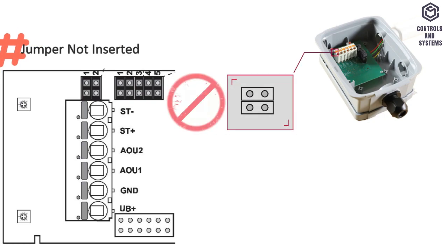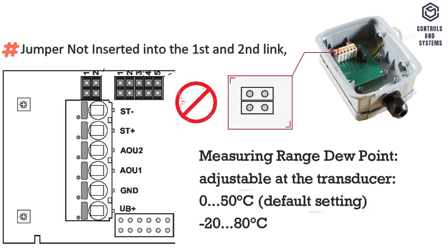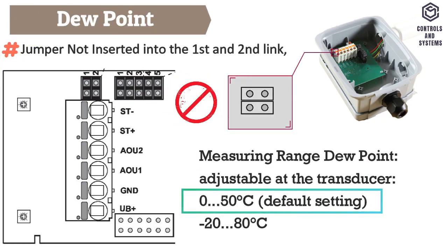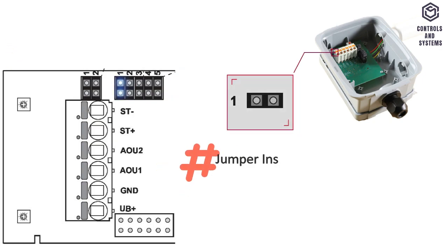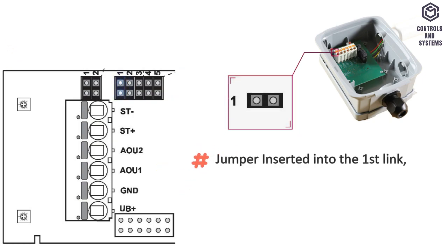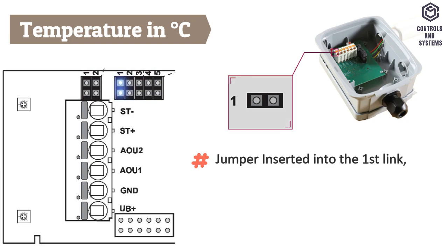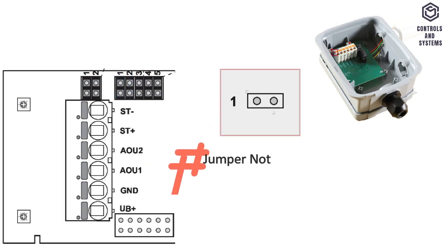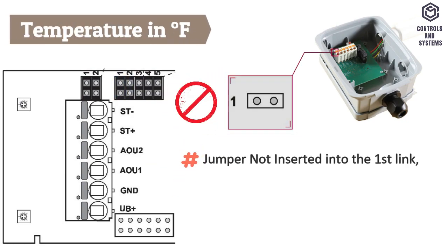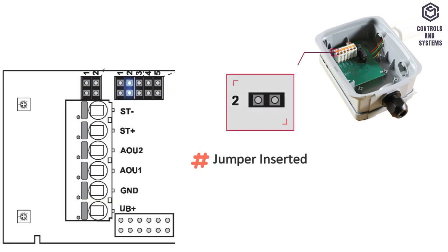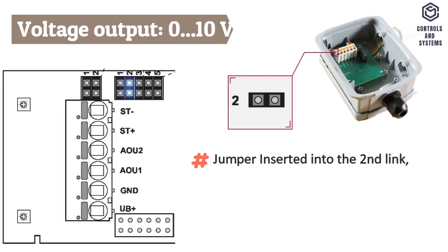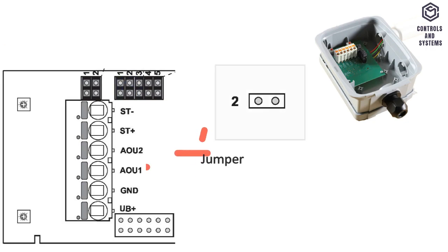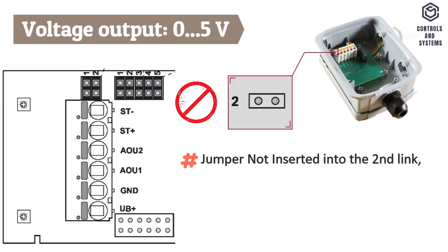If the jumper is not inserted in terminals 1 and 2, the sensor will show the dew point value. If a jumper is inserted in the first terminal, the sensor will show the temperature values in Celsius. If the jumper is removed, the sensor will show the temperature values in Fahrenheit. If a jumper is inserted in the second terminal, the sensor output value is 0 to 10 volt. If the jumper is removed, the sensor output value is 0 to 5 volt.